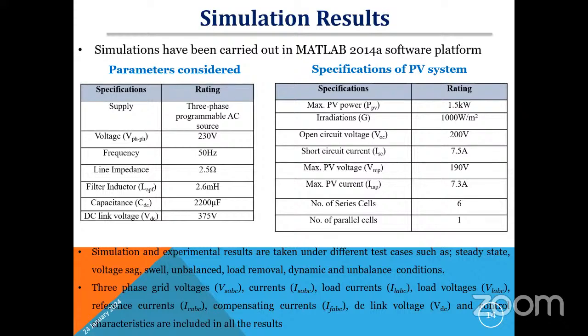Here we have considered a PV system in this particular paper. The maximum power is 1.5 kilowatt, irradiance 1000 fixed, open circuit voltage 200, short circuit current 7.5 ampere, maximum voltage 190 volt, and maximum PV current 7.3 ampere after the boost converter. The number of series cells is 6 and parallel cells is 1. Why did we consider these ratings? Because in my university we developed a prototype experimental setup using these parameters.